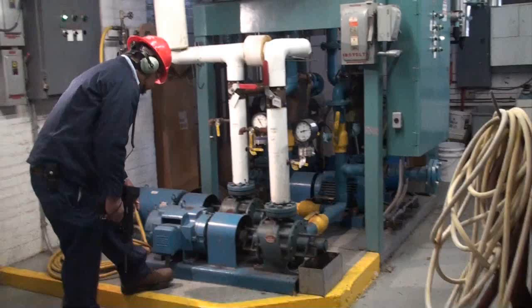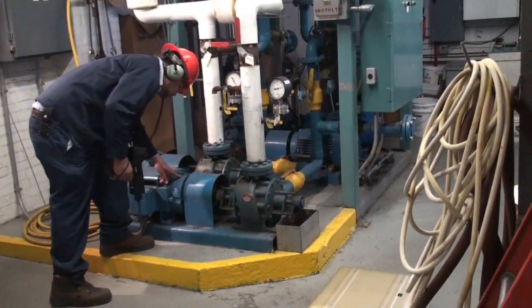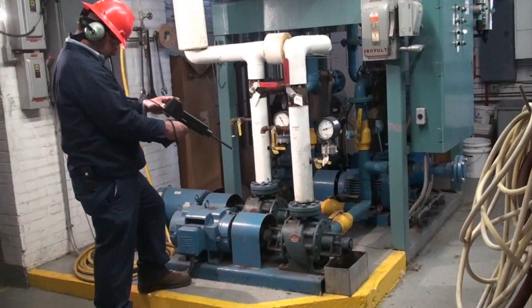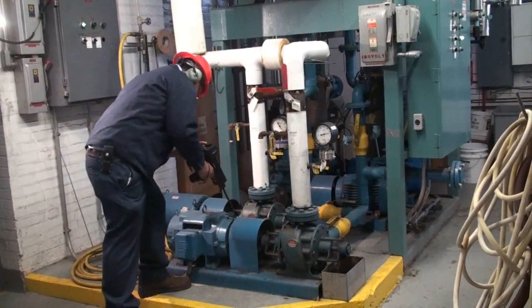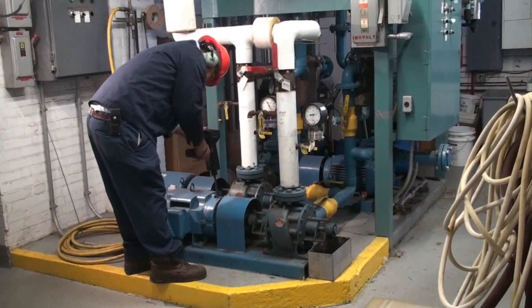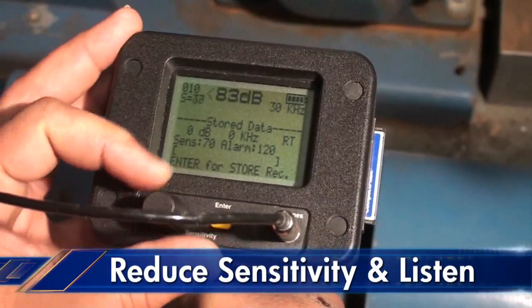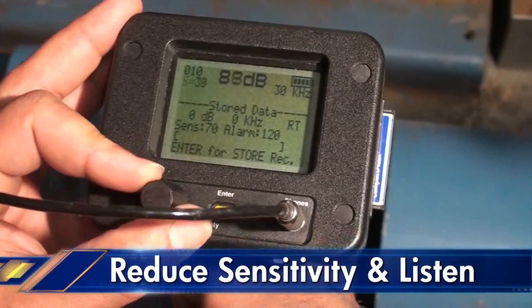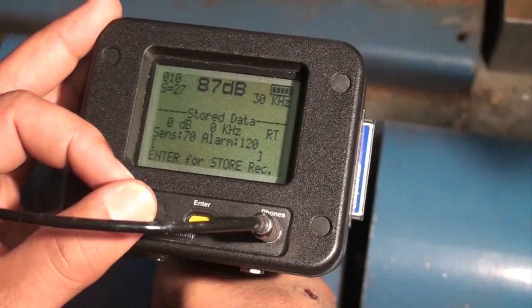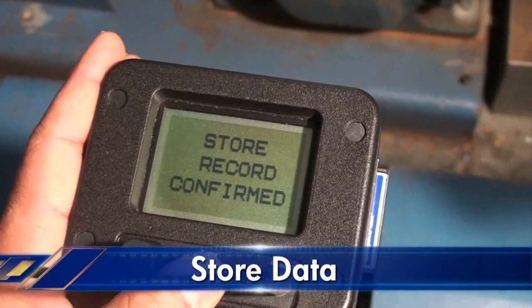Now let's go and check a bearing. First we'll check the identification tag to see if it conforms to the test number in our route. Then we'll touch the bearing and reduce the sensitivity to hear the bearing more clearly. When ready, we'll store the data, which we can then download into our software. We can also record the bearing sounds and store the sounds along with our data for detailed analysis to enhance our diagnosis.